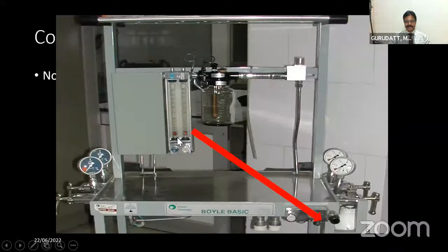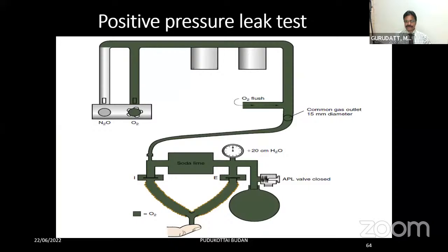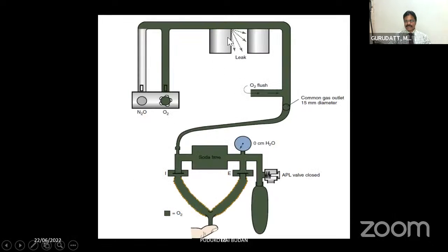One thing again is that there is actually no safety feature or safety measure between the flow meter assembly and the common gas outlet, even in modern workstations. That is the reason if there is any leak here, you will not know at all, and you can still provide a hypoxic mixture. So you have to go for the positive pressure leak test or the negative pressure leak test. In the positive pressure leak test, you pressurize the system to 20 centimeters using the oxygen flush, and this pressure should be sustained for about 10 seconds. You also open the vaporizers and again check whether there is any drop in pressure, which would indicate a leak in the vaporizer.